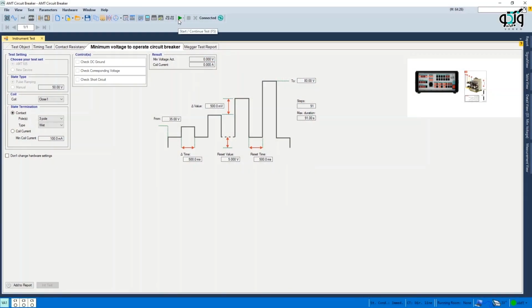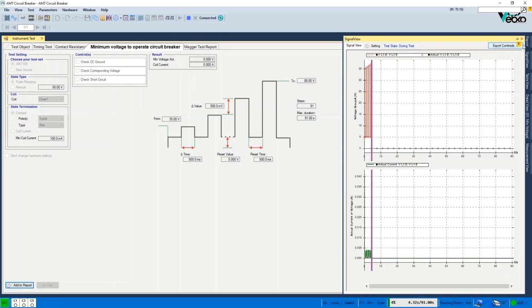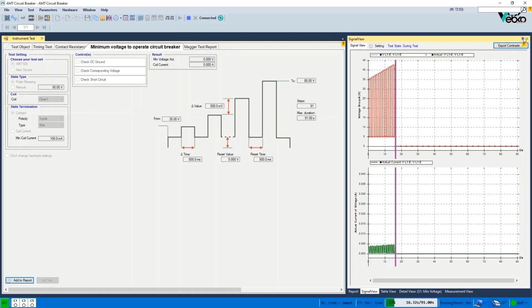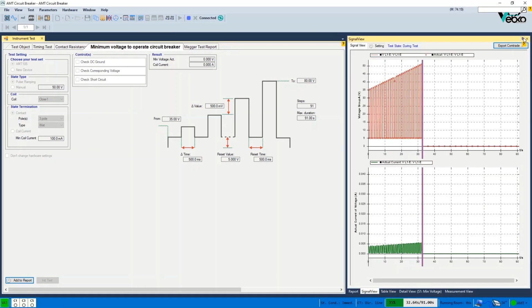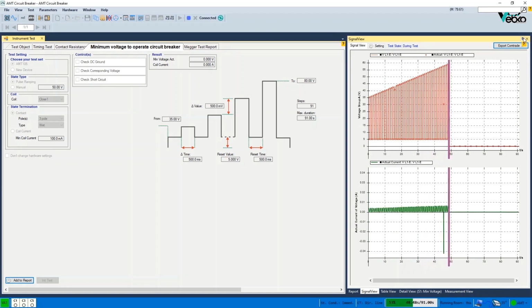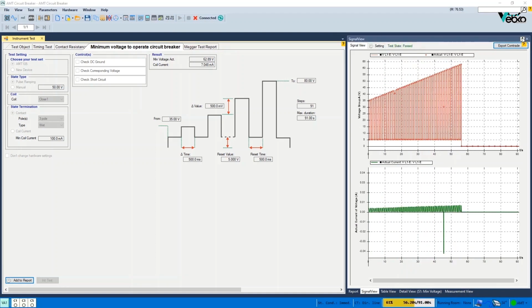After selecting Coil Close 1 and adjusting the wiring, Init test is selected and the test runs. By opening the signal view window, you can view the applied voltage as well as the injected current. After the circuit breaker operates, the minimum operation voltage along with the amount of current drawn during the operation is displayed in Results section. By selecting Add to Report, the test result is added to the Output report.